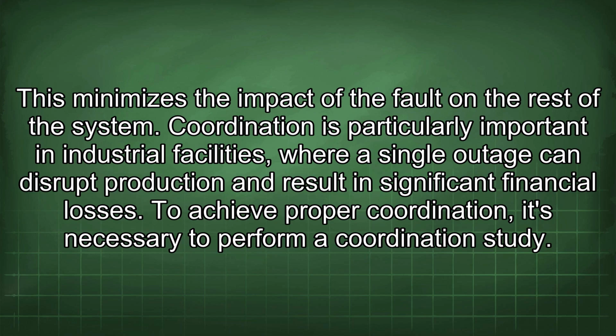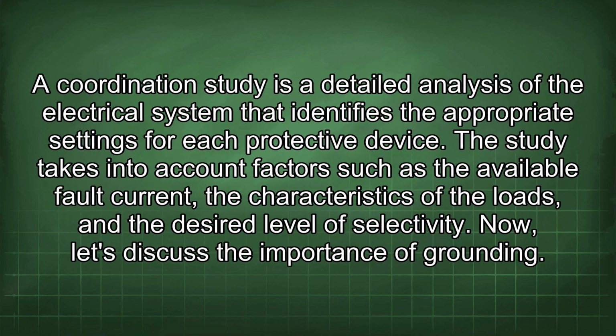To achieve proper coordination, it's necessary to perform a coordination study. A coordination study is a detailed analysis of the electrical system that identifies the appropriate settings for each protective device. The study takes into account factors such as the available fault current, the characteristics of the loads, and the desired level of selectivity. Now, let's discuss the importance of grounding.